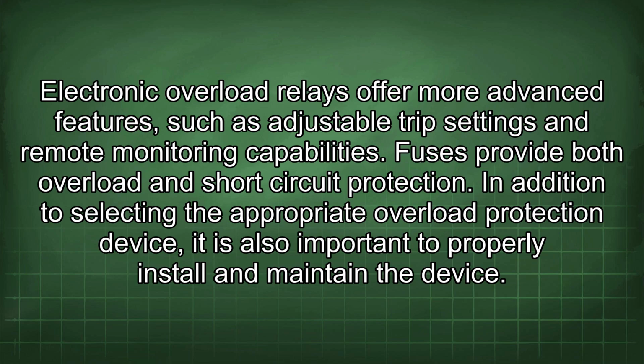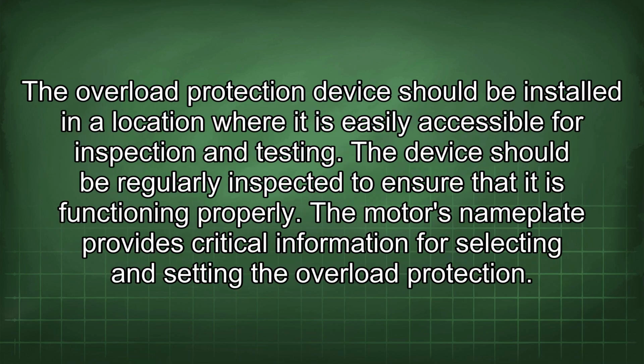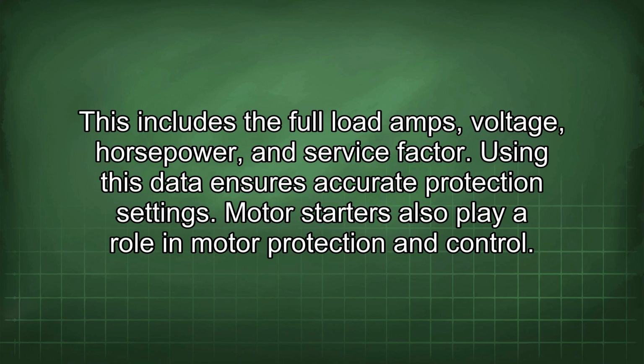In addition to selecting the appropriate overload protection device, it is also important to properly install and maintain the device. The overload protection device should be installed in a location where it is easily accessible for inspection and testing. The device should be regularly inspected to ensure that it is functioning properly. The motor's nameplate provides critical information for selecting and setting the overload protection. This includes the full load amps, voltage, horsepower, and service factor. Using this data ensures accurate protection settings.